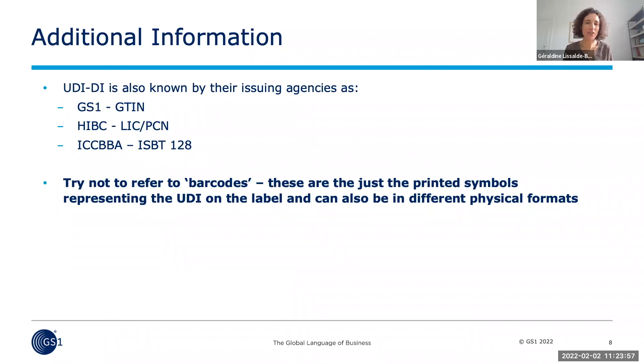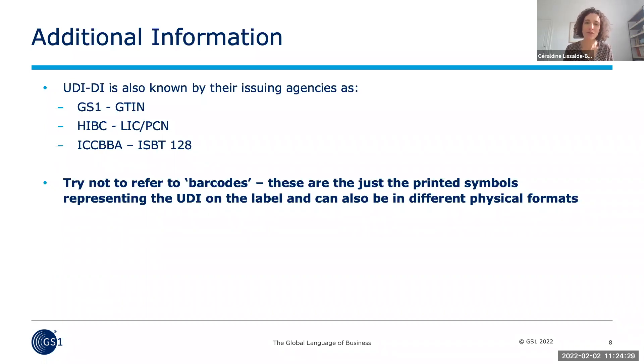The UDI in GS1 terms is called a GTIN — a Global Trade Item Number. But GS1 is not the only issuing agency for unique device identifiers as per global UDI requirements. You also have HIBC with their own version, and ICCBBA related to blood and human tissue devices. What's important is that the shortcut is easy to make — referring to UDI as a barcode — but really the barcode is just the carrier. The important part of the UDI is the identifier itself, which enables you to ensure your device is globally and uniquely identified, both along the supply chain and for use at the point of care.